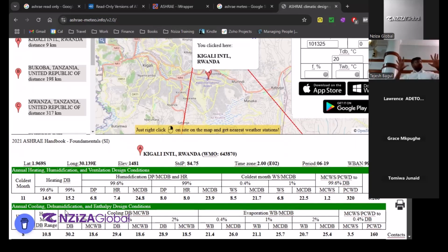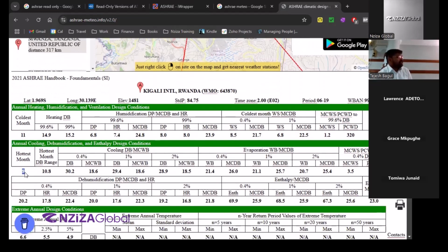Now, whether we debate it or not, global warming is real. The temperatures are slightly increasing every year. I've got projects in Saudi that worry about those peak seasons, and then it becomes very hot over there, and the HVAC unit cannot sustain the load. In that case, this comes into the picture. Talking about the cooling, the hottest month, as per the data, is August in Kigali. In the hottest month, for 0.4% of the time, the temperature will be 30.2 degrees centigrade dry bulb.